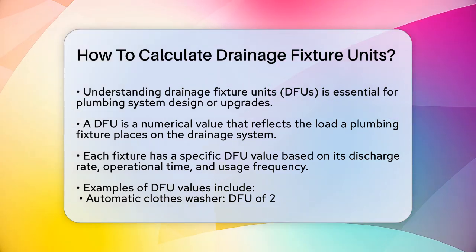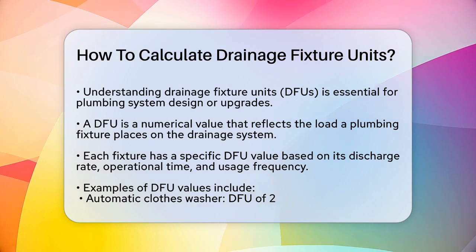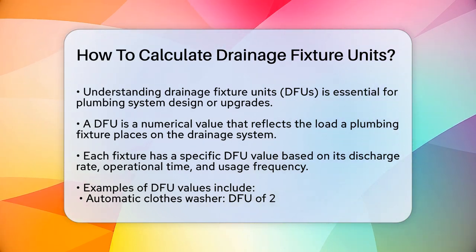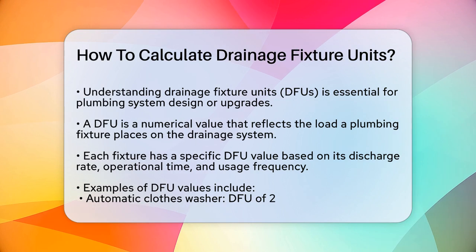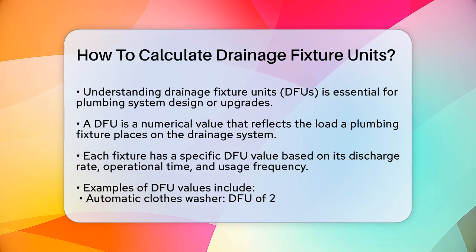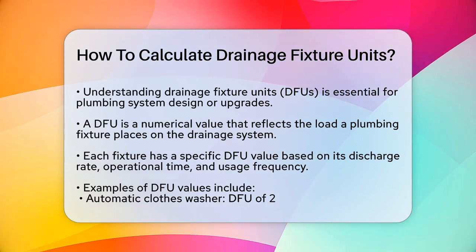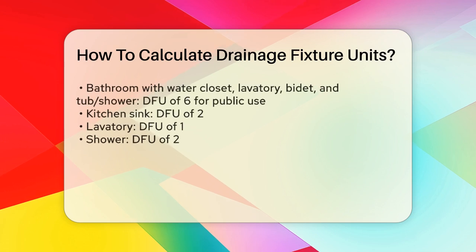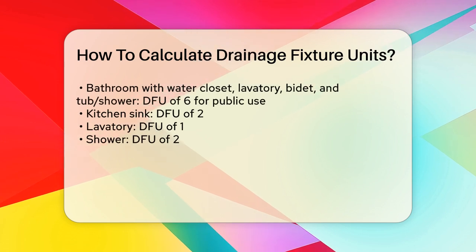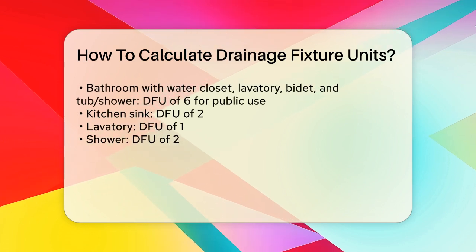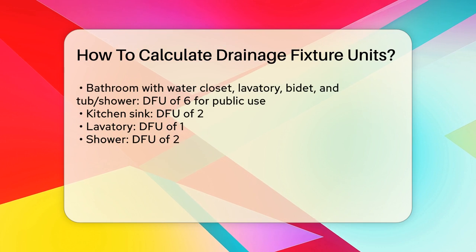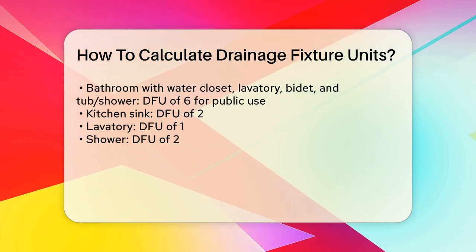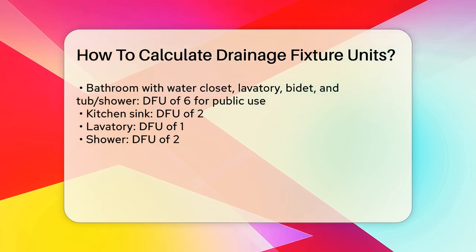To start calculating DFUs, you need to identify the types of fixtures in your system. Each fixture has a specific DFU value. For example, a residential automatic clothes washer has a DFU of two, while a bathroom that includes a water closet, lavatory, bidet, and tub or shower has a DFU of six for public installations.